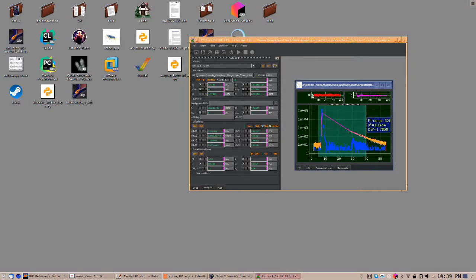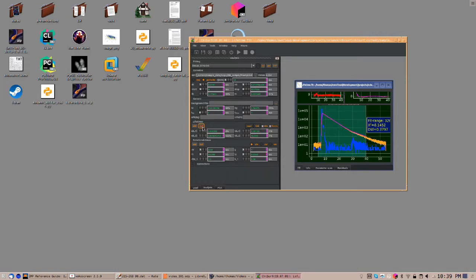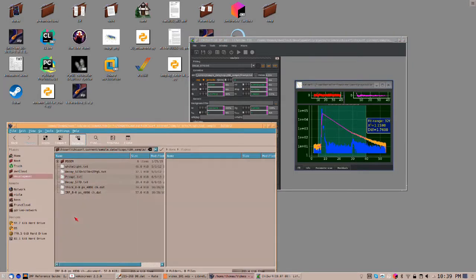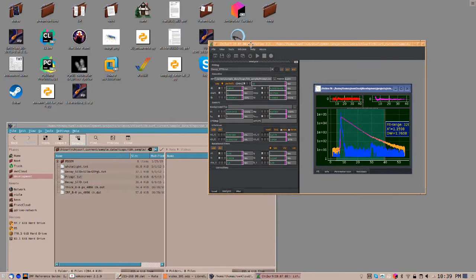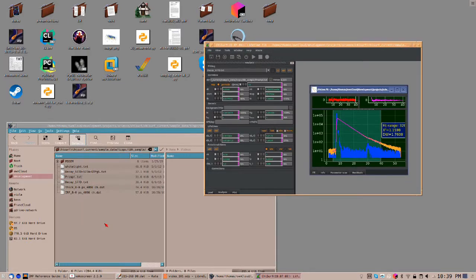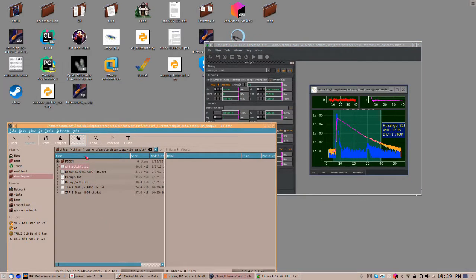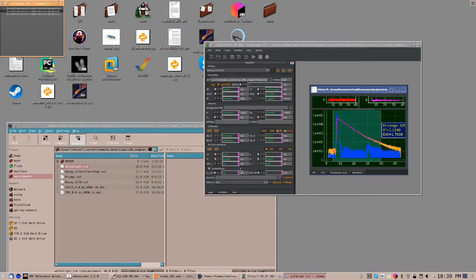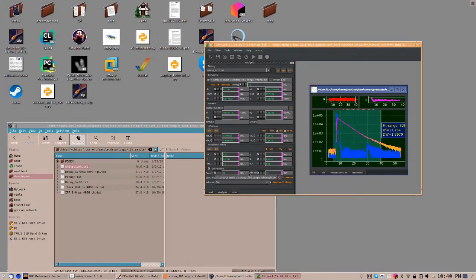Adding more fluorescence lifetime components to the model does not improve significantly the fit quality. Nevertheless, this model cannot describe all the features in the data. In this particular dataset, the reasons are differential nonlinearities that are not considered yet. You can correct differential nonlinearities by using or recording a linearization table using uncorrelated light. In the example data folder, the file recording the uncorrelated light is called white light. When you click here on the lower button on Corrections, you can select a dataset that corresponds to the linearization table. You can see here the fit is already much better.